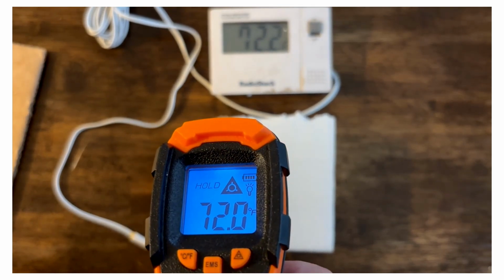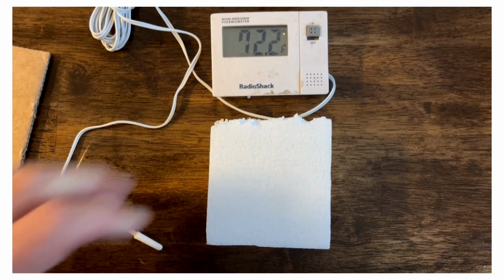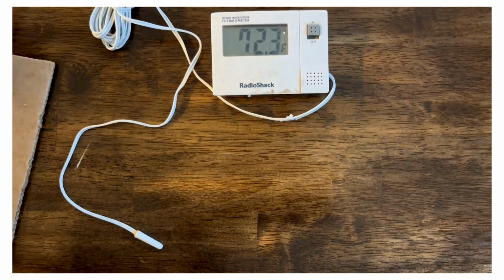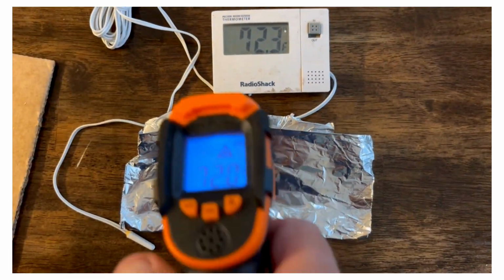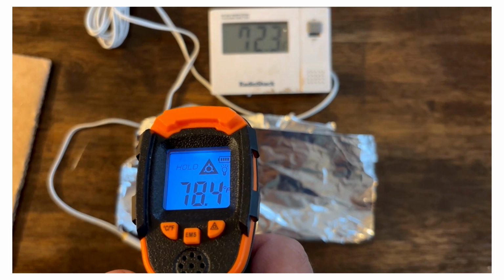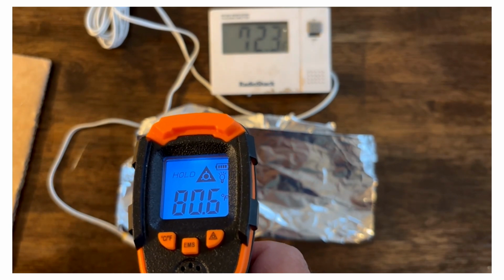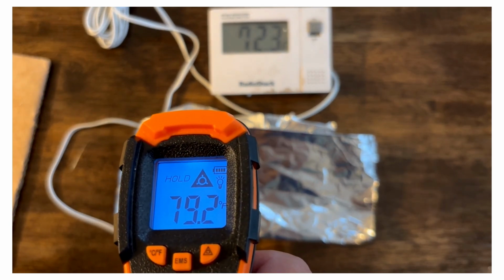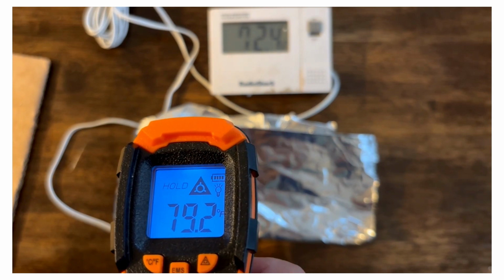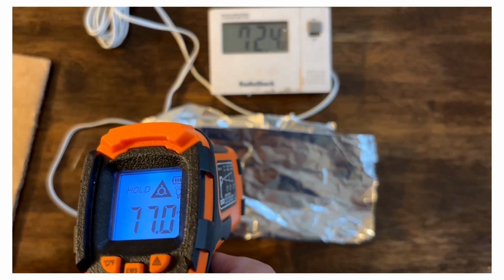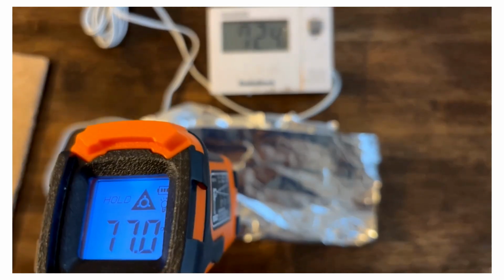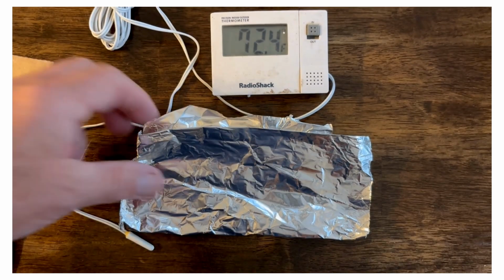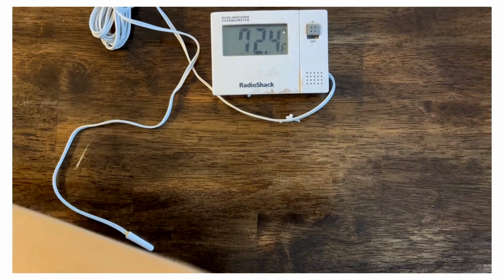We'll find out about emissivity later. It's got a mid-range emissivity. And this was a piece of aluminum foil, and it gave not a very good reading at all, just because it's so reflective. It has a very low emissivity and a high reflectivity, and it gets all kinds of stray radiation that messes up your readings. So you'll get a wide variation in aluminum foil or anything reflective.